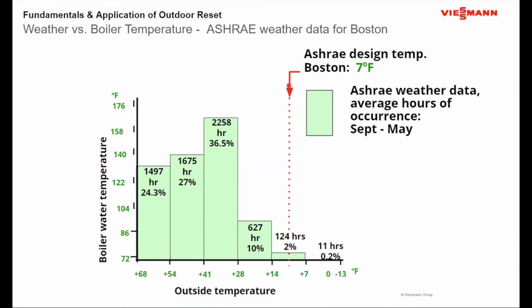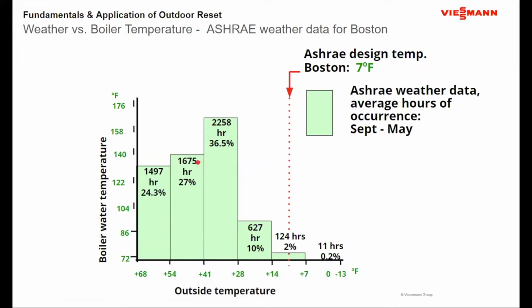So we design for 2% of the heating season because the goal is to be comfortable under design conditions. But when you start to look at these numbers, you notice when I look at the bins up here, above 28 degrees Fahrenheit, above 41 degrees Fahrenheit, above 54 degrees Fahrenheit, this represents a large portion of the heating season. And under these conditions, I do not need the same amount of energy that I do on my design day of 0 degrees Fahrenheit.